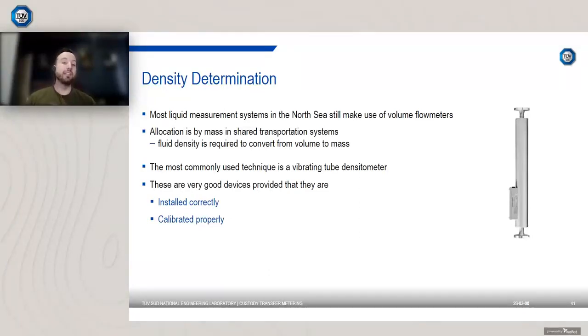So density determination. Why would you want to characterize the density of your fluid? In relation to liquid systems, especially in the North Sea, many still make use of volumetric flow meters. So if you've got a volumetric flow meter, but you need to know the mass of your fluid, how do you get mass from volume? Well, you need to know the density. It's especially important for allocation because this is typically done by mass. So in order to get mass, you're going to need some form of density measurement, unless you're using a Coriolis meter, which will give you the mass directly.